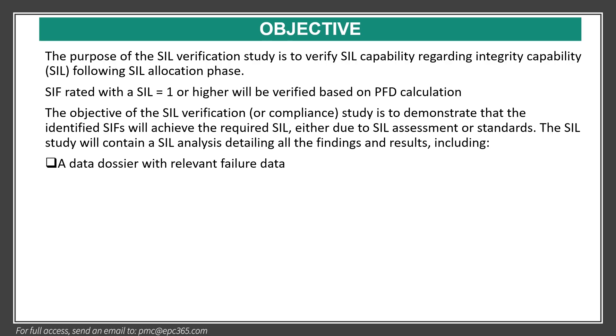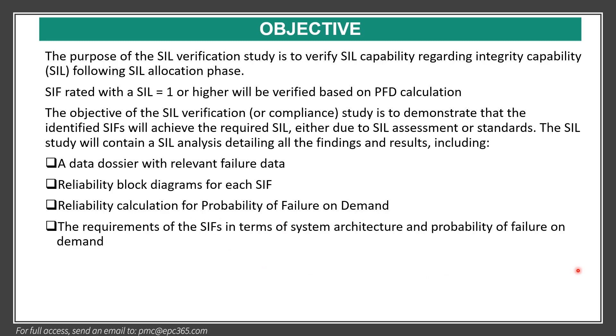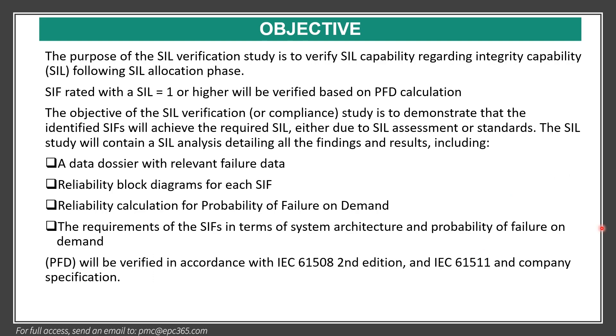The objective of the SIL verification or compliance study is to demonstrate that identified SIFs will achieve the required SIL, either due to SIL assessment or standards. The SIL study will contain a SIL analysis detailing all findings, including a data dossier with relevant failure data, a reliability block diagram for each SIF, reliability calculation for probability of failure on demand, and requirements of the SIF in terms of system architecture and PFD. PFD will be verified according to IEC 61508 second edition, IEC 61511, and company standards.